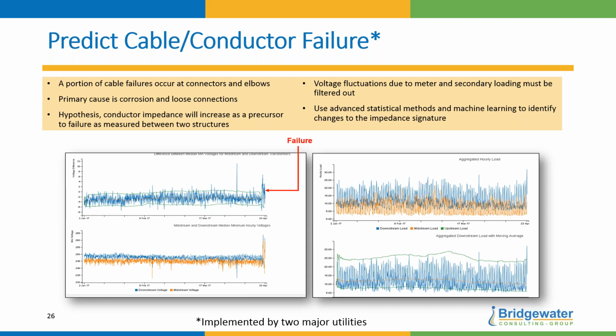So we developed a series of analytics to filter that out—grouping meters, standard deviation, statistical analysis—and came up with a plot that shows there were some issues prior to the failure. Luckily I had failures, so I was able to go back and see if there were precursors to them. And there were, in a chunk of cases, around 20 to 25%.